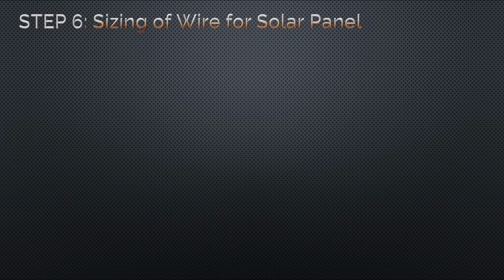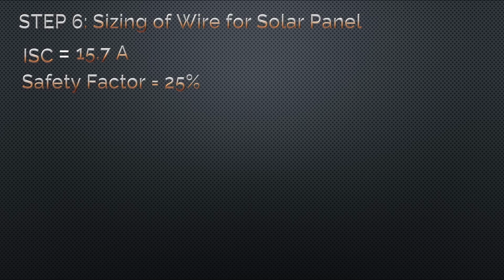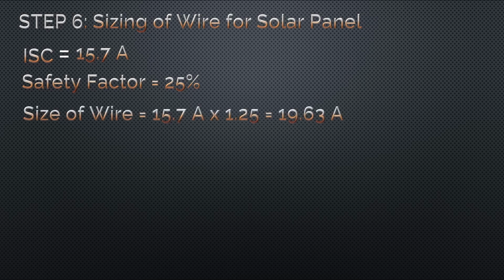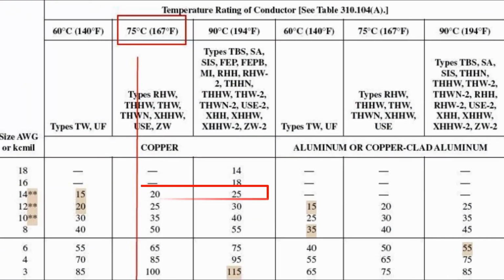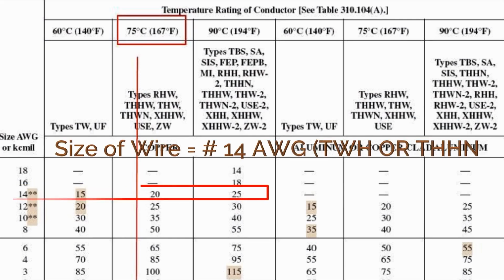So dito na tayo sa step 6, which is the sizing of feeder wire for solar panel. Sizing of feeder wire for solar panel is the same as sizing of the circuit breaker in terms of parameters to be used. Those parameters are short circuit current and 25% safety factor. In this case, the 25% factor is a safety measure to account for potential overloads or surges in current that a solar panel system might experience. So the size of wire should be rated at 19.63 amperes.